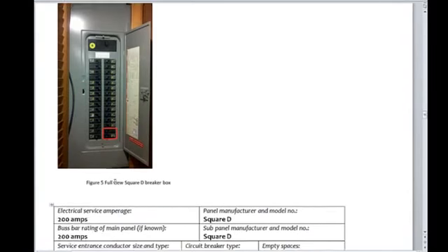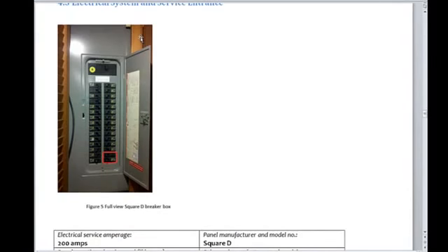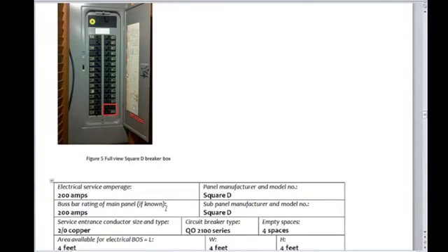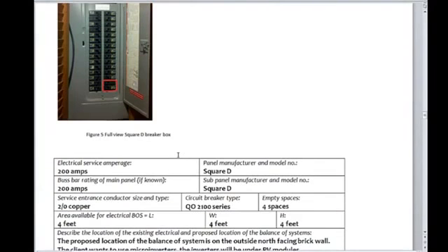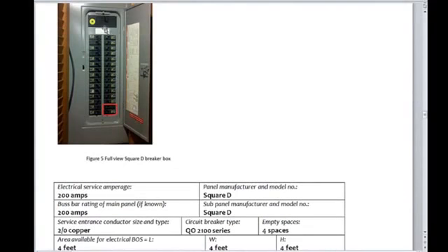And this was difficult, it's hard to see, but this was a nicely done wood type of panel that went over their disconnect. You know, it looked nice, but we weren't able to see what the disconnects were. I was able to shine a flashlight, look in there, and I could see that it was a 200 amp disconnect, and I was able to look from the side and see what the wires running into the service were, and that was a 2-aught wire. So you want to make sure that the nameplate is there and that sort of thing.